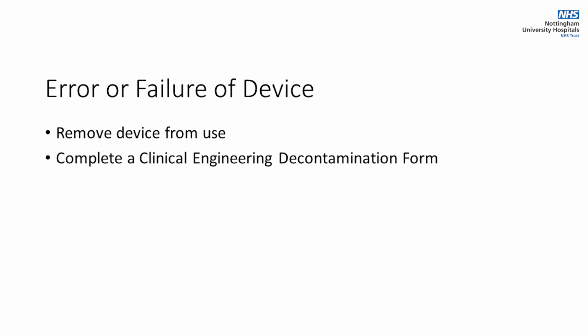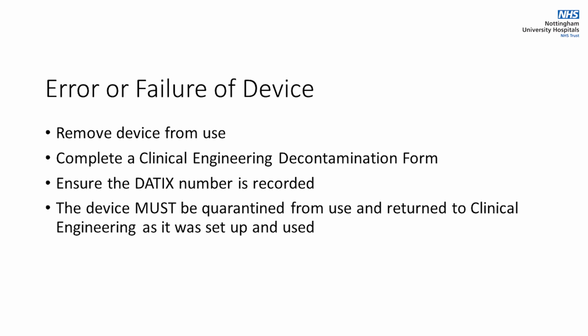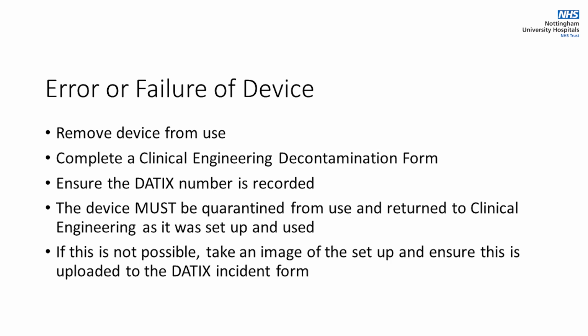What actions to take if there is an error or failure of the device? Remove the device from use after ensuring the patient is safe and unharmed. Complete a clinical engineering decontamination form detailing any error codes or messages. If the device is involved in an accident, ensure the DATIX number is recorded on the decontamination form. The device must be quarantined from use and returned to clinical engineering as it was set up and used, including any consumables used. If this is not possible, take an image of the setup and ensure this is uploaded to the DATIX incident form.